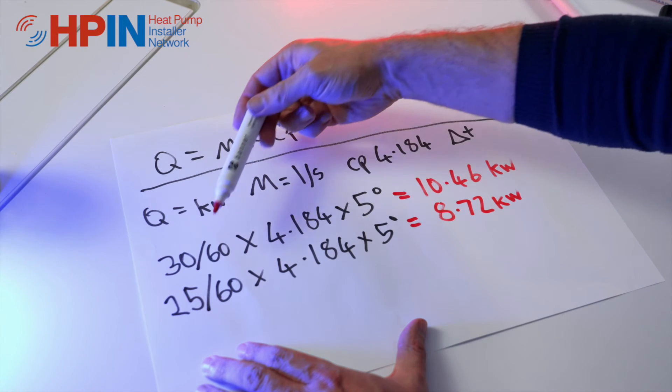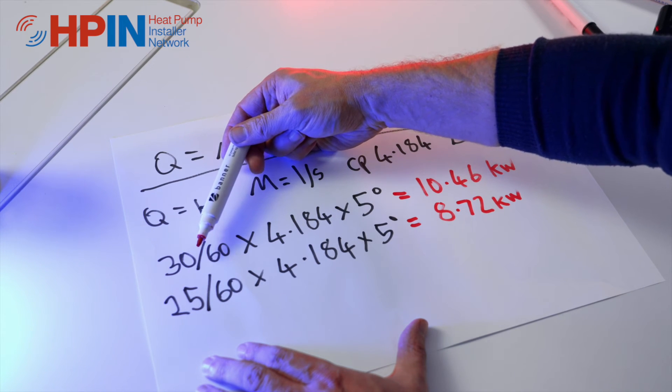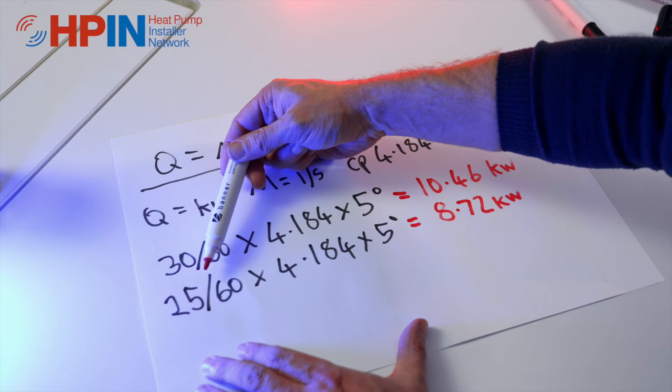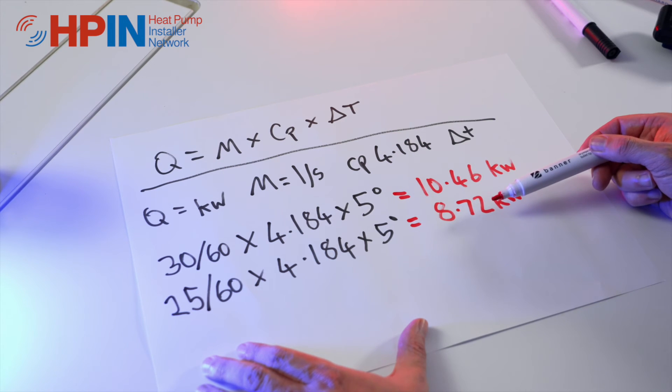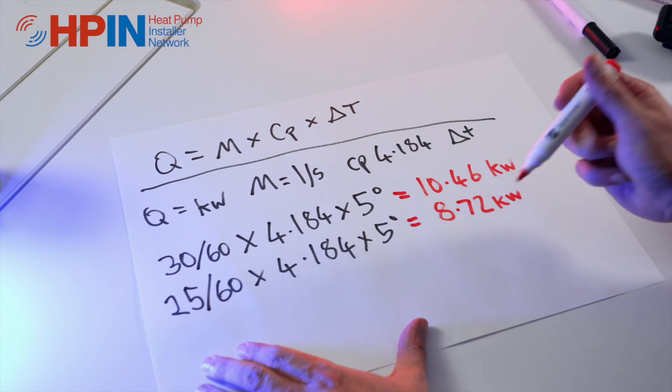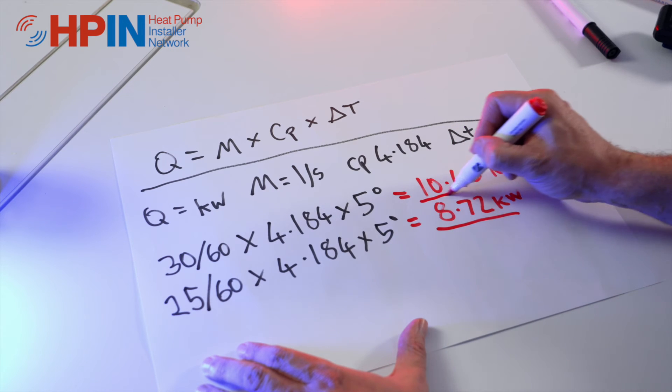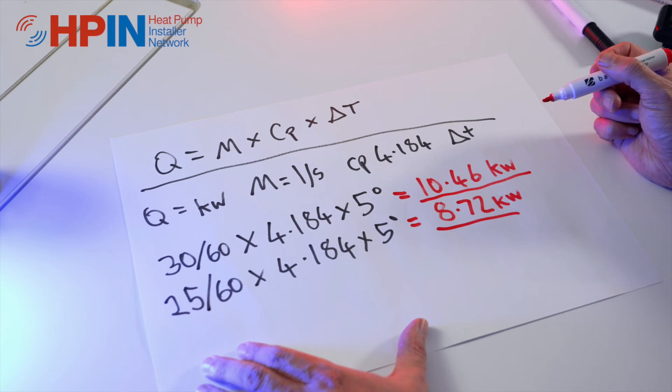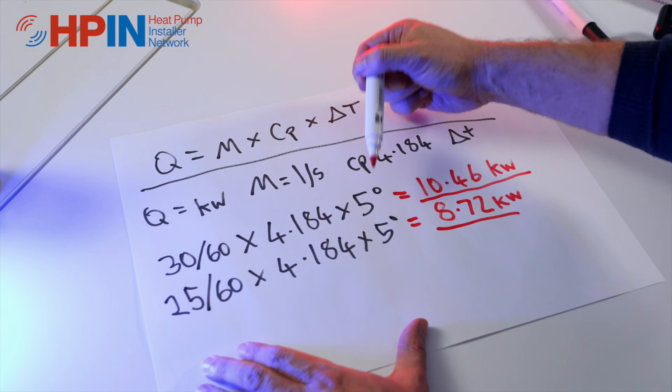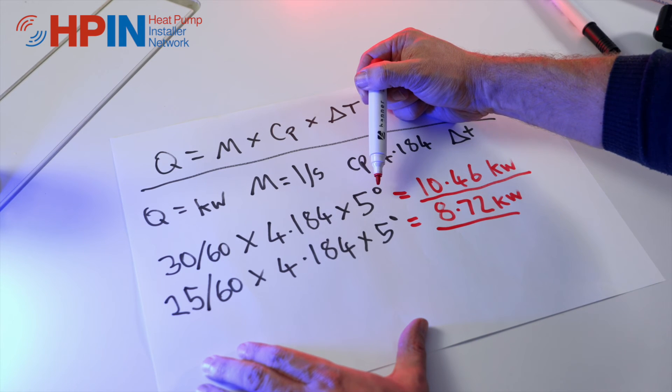So from just dropping our flow rate by 5 litres a minute, I've made a massive difference to the kilowatt output that I'm getting. And that's why flow rates are so important to heat pumps, especially with our 5 degree delta T, our lower delta T.